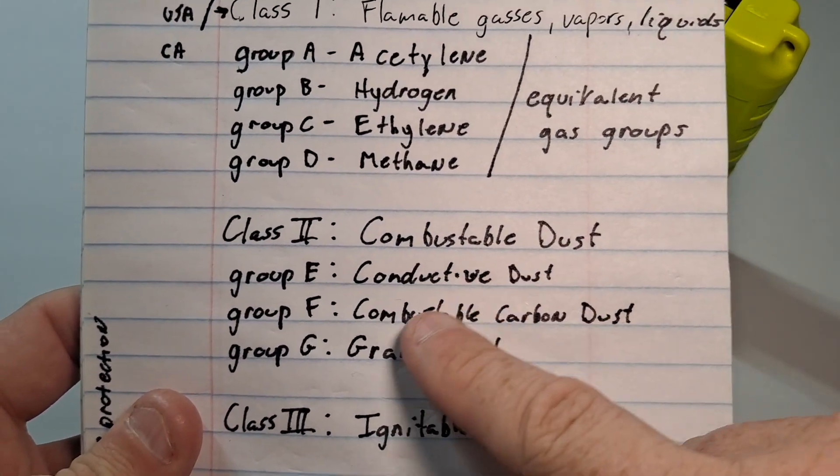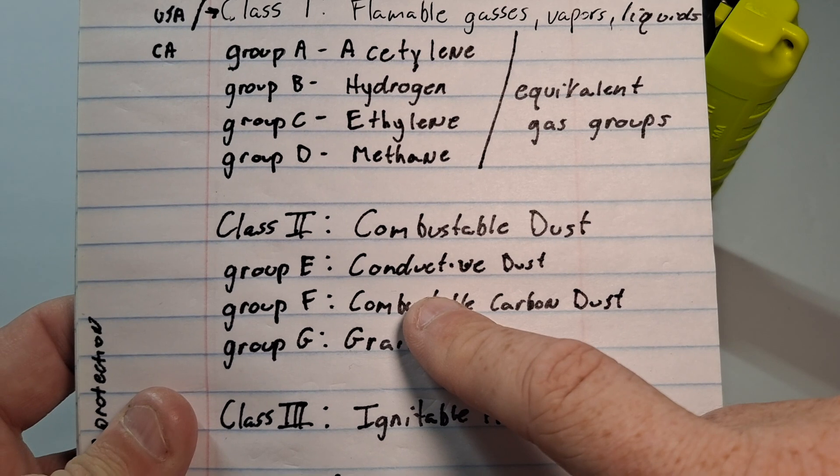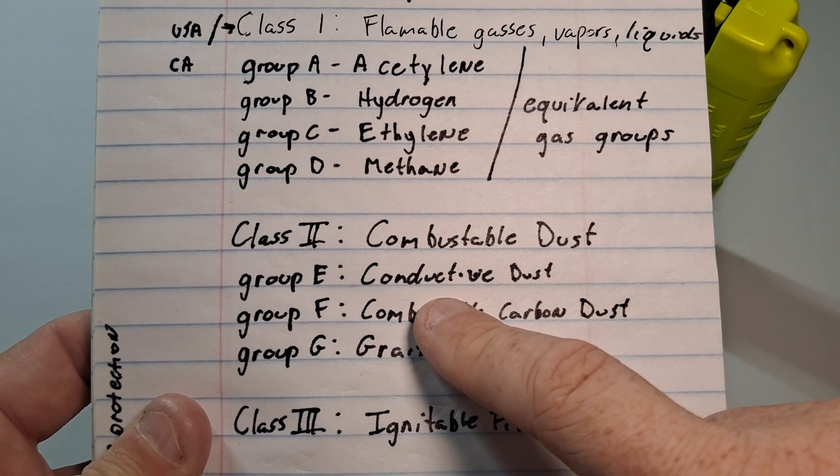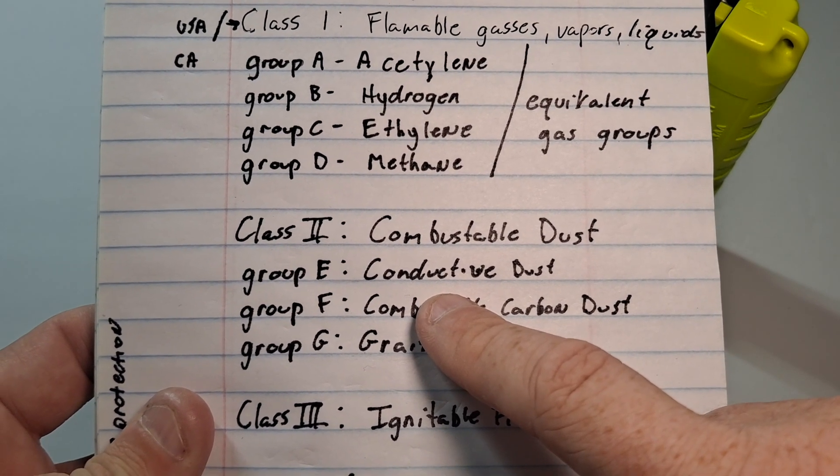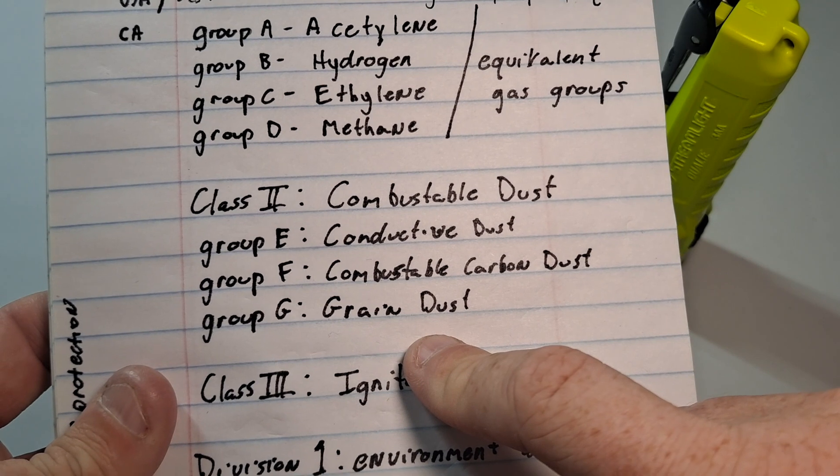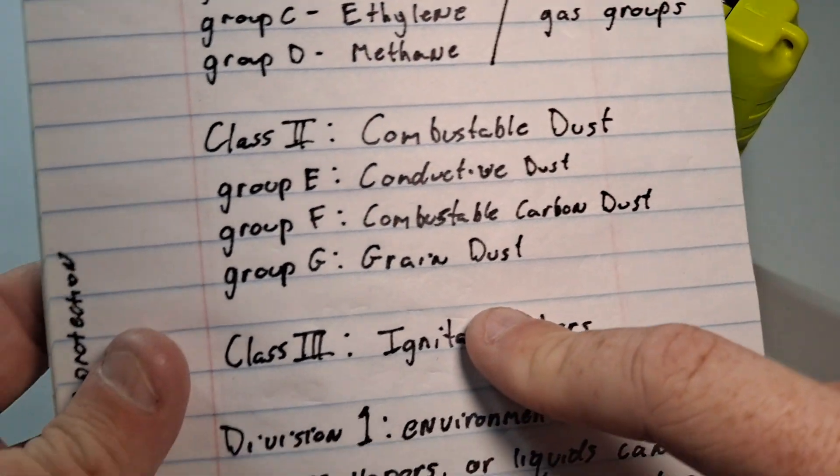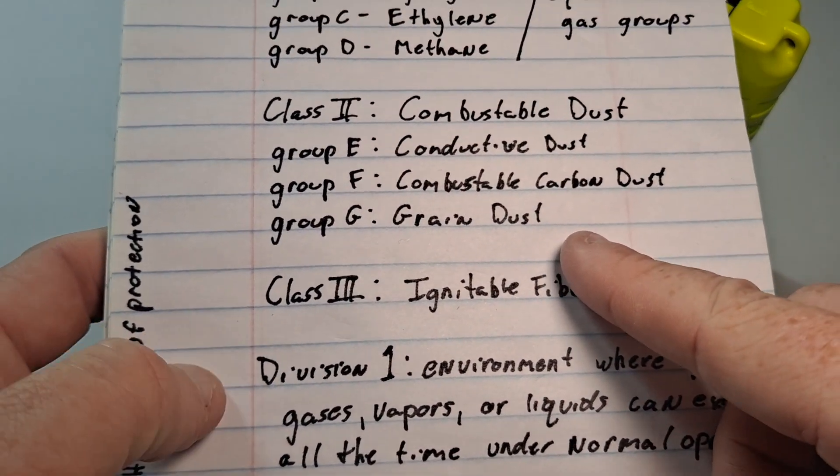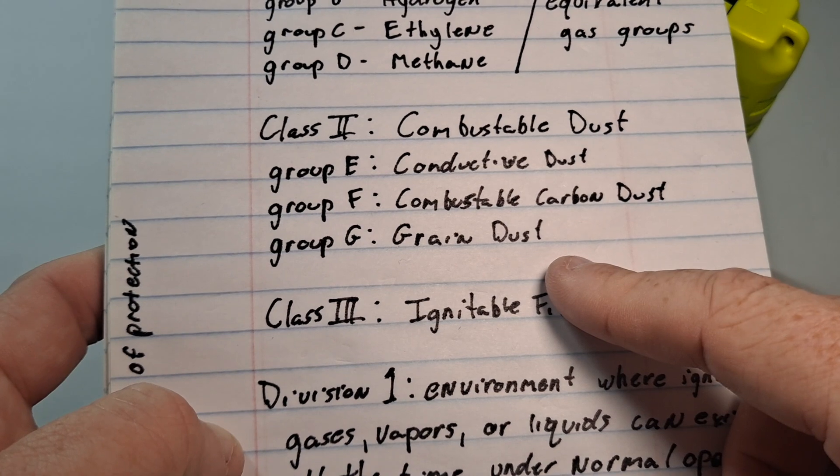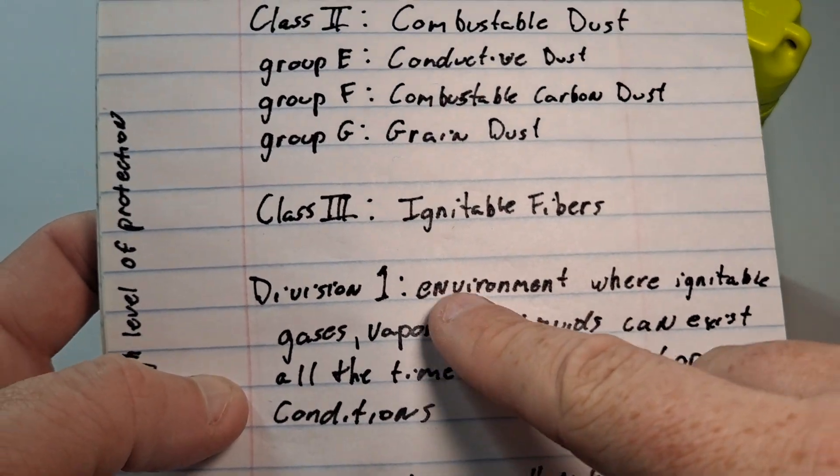Class two combustible dust. Group E conductive dust. So types of sand or types of gritty material that conduct electricity. Group F combustible carbon dust and group G grain dust because a lot of people don't realize that grain silos are just an explosion waiting to happen. They have things to help mitigate the dust in them but the dust in the silos get electrically charged. You just need an outlet or a ground and poof one of those things explode. That's why they're all in the shape of rockets. Just kidding.